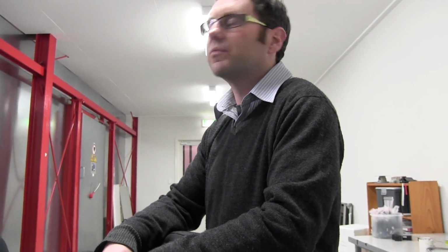Not many. It's small things like the fibre optics, setting them up properly, and just the way we like it, the way we want to use it. You customise it for your particular uses, so that it fits our equipment. With the very high frequency stuff, the cables have too much attenuation, so we have to do testing inside the room. We move the test receiver in and sit in there on a wee desk. Would you shield the gear when it's in there? No, it's only the really high frequencies, and they're very directional, as you can imagine. So we haven't had a problem with what we've been measuring.